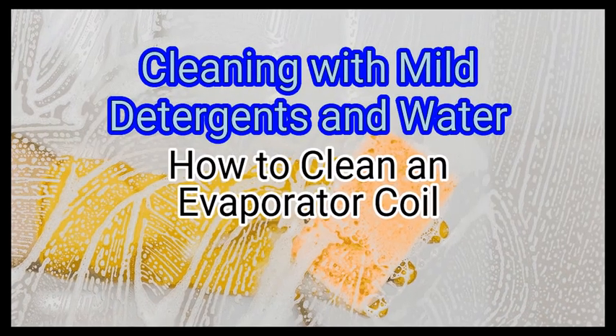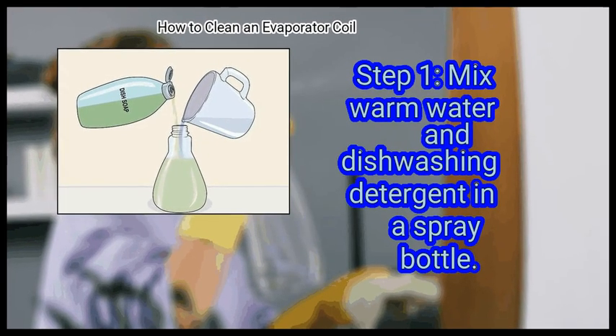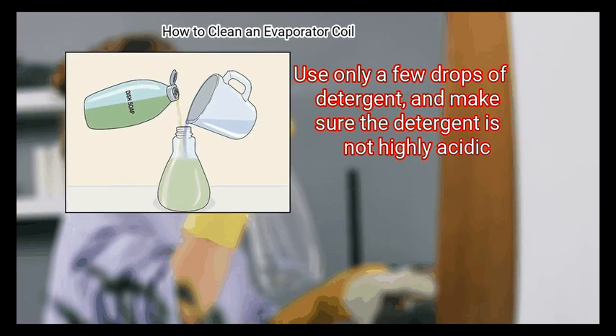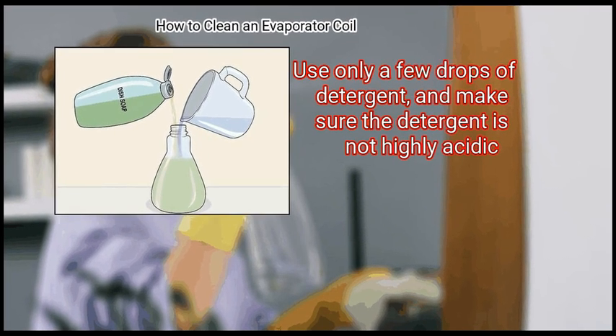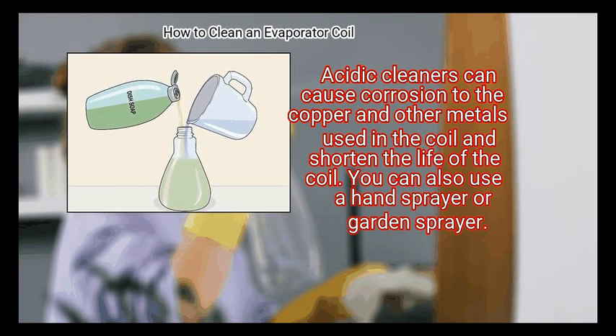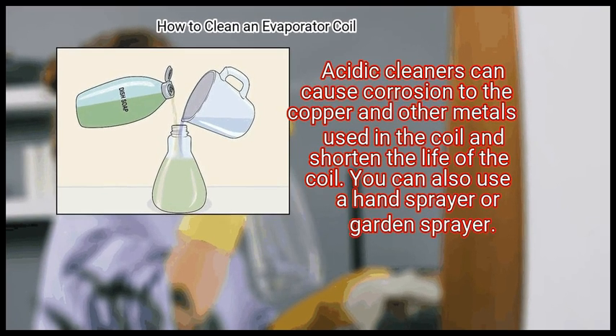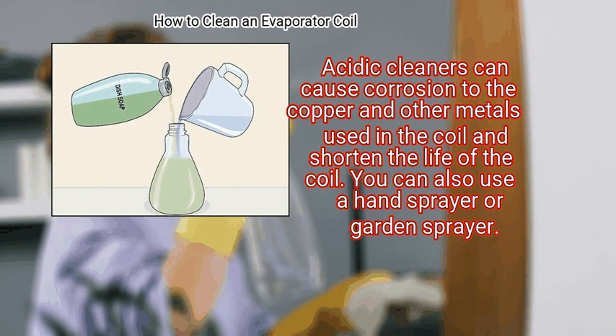Method 3. Cleaning with mild detergents and water. First, mix warm water and dishwashing detergent in a spray bottle. Use only a few drops of detergent, and make sure the detergent is not highly acidic. Acidic cleaners can cause corrosion to the copper and other metals used in the coil and shorten the life of the coil. You can also use a hand sprayer or garden sprayer.